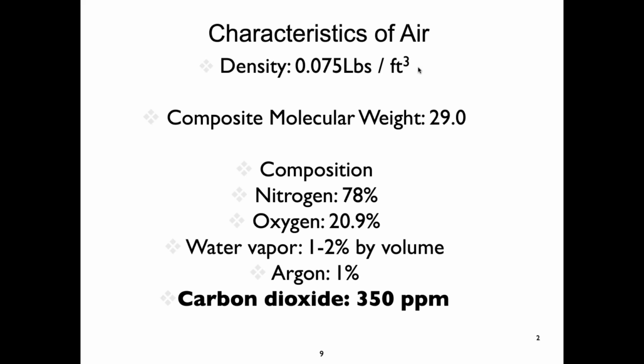So carbon dioxide is important to us, right? And the ASHRAE standard helps you define if you're getting enough ventilation with outside air by setting a limit on the amount of CO2 in the air. So in other words, if it's 400 parts per million outside and 1300 parts per million inside, maybe we're not getting enough ventilation with outside air. The standard roughly defines enough exchange with outside air as staying below 700 parts per million over the levels outdoors.